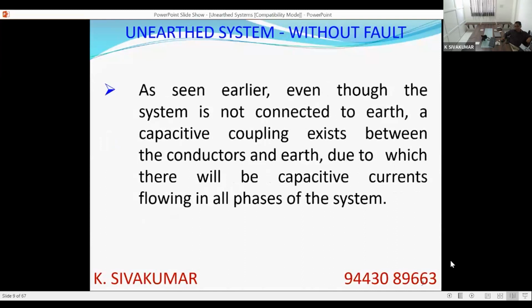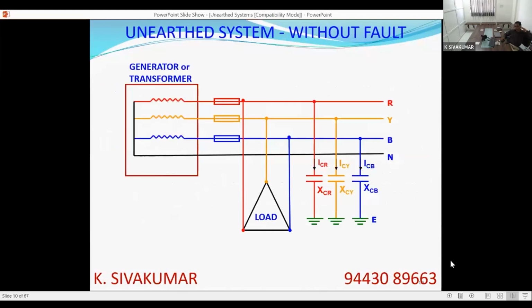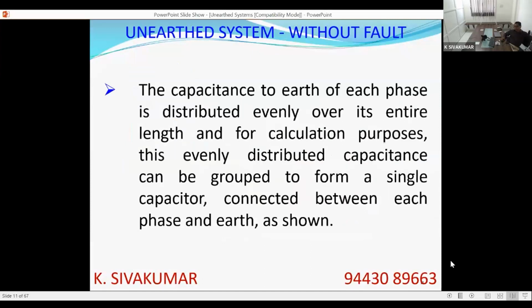Now, even though the system is not connected to earth, a capacitive coupling exists between the conductor and earth, due to which, whenever there is a capacitance, there will be capacitive currents flowing in the system. So when we have XCR, XCY, and XCB, you will also have ICR, ICY, and ICB. These capacitive currents will start flowing in the system through the earthed coupling capacitors. The capacitance to earth of each phase is distributed evenly over its entire length, and for simplicity of calculation, we assume this to be a bulk capacitor connected between each phase and earth.